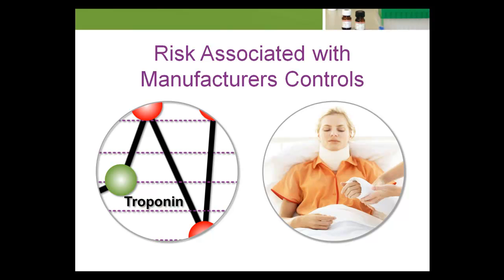Conversely, those laboratories that were testing a third-party, independent control saw variation in these controls, along with variation in patient samples. Customer calls ultimately led the manufacturer to identify and correct an instrument problem.